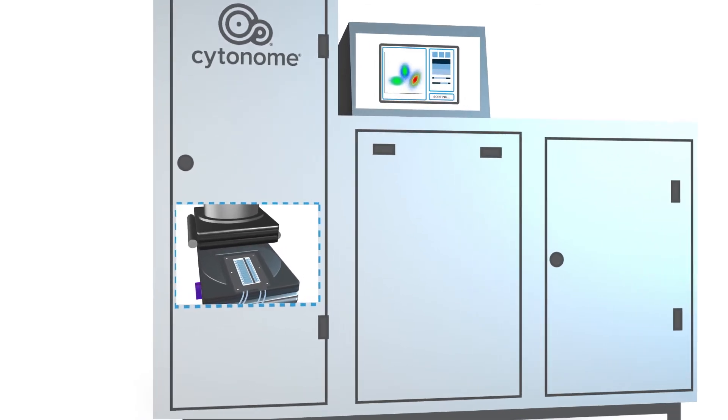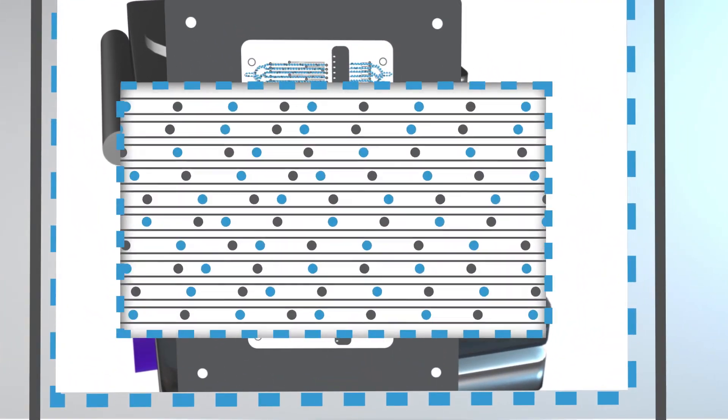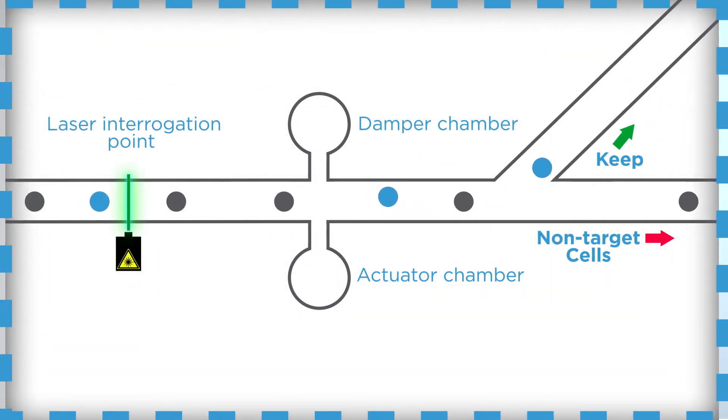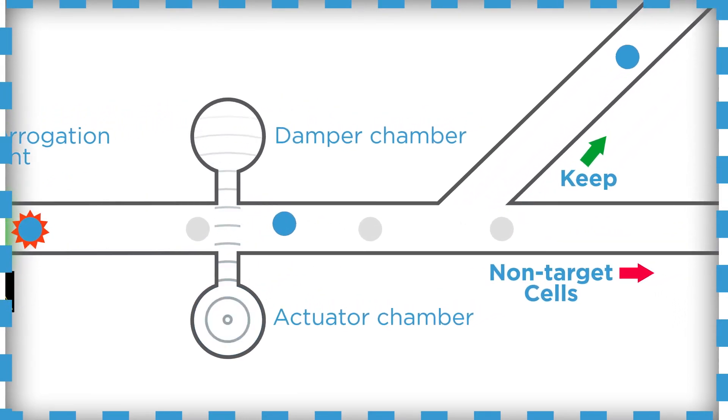High purity cell populations are a critical requirement for the successful manufacture of many cell therapies. In each microsorter channel, cells pass the laser interrogation point and then the target cells are selected with a gentle push that directs them into the keep with the rest of the sorted cell sample, while non-target cells are segregated and collected.